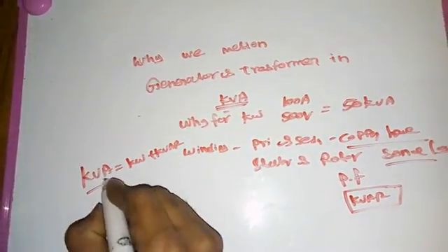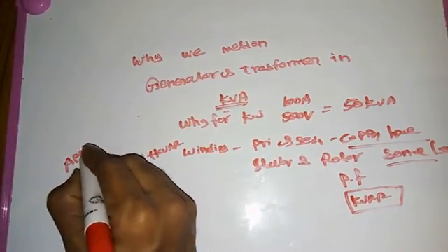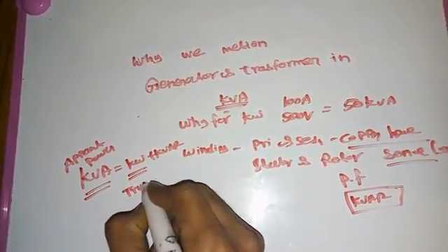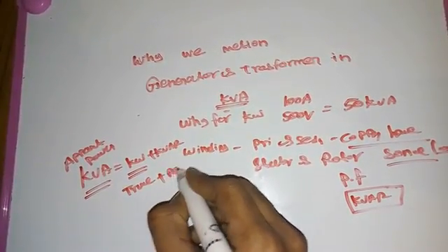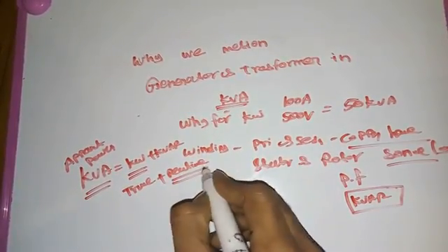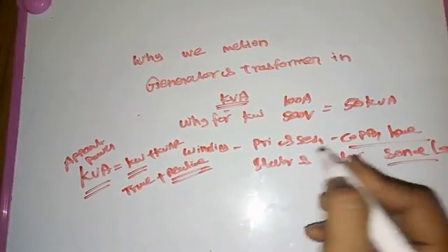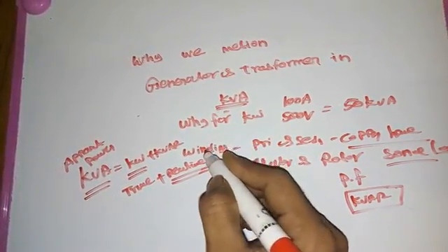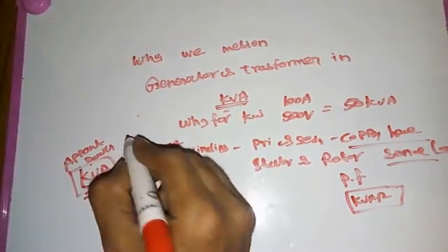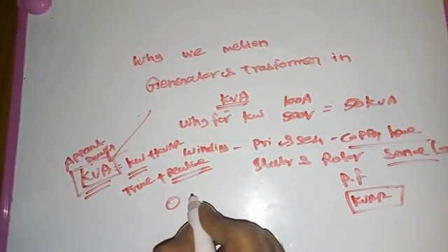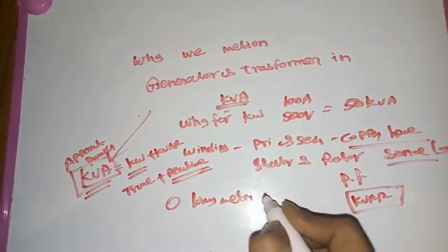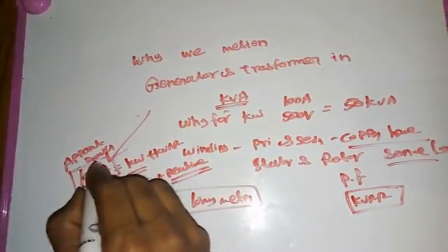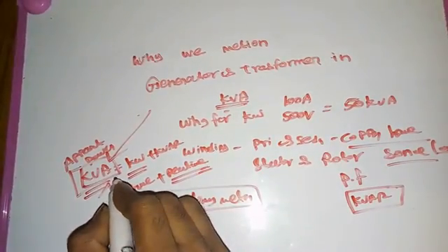KVA is apparent power. KW is true power, or real power. KVAR is reactive power. Reactive power is very important because the coil windings have copper losses, insulation losses, and winding losses. These are the losses available in our transformer and generator. No zero-loss material has been invented yet, so that's why we always mention generators and transformers in KVA.